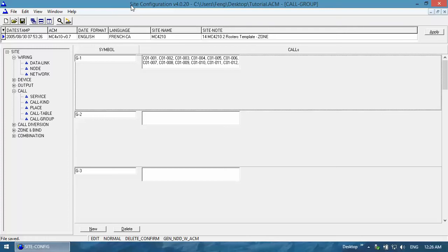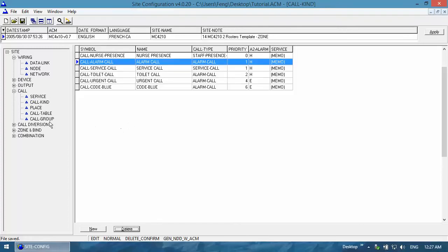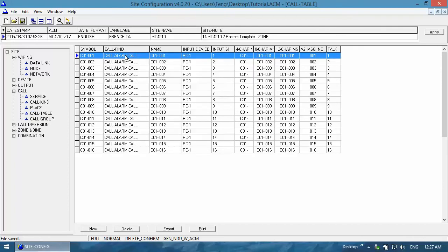So you have the choice between connecting it to, let's say, the presence, the patient call, the emergency, or the bathroom. Usually it would make a lot of sense to connect it next to the patient call because that's where it's closest to the patient, to the bed. But it all depends on your room configuration.